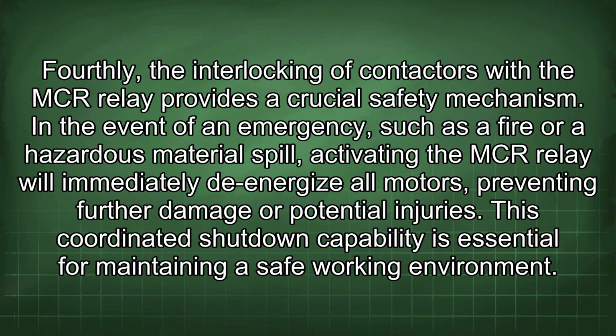Fourthly, the interlocking of contactors with the MCR relay provides a crucial safety mechanism. In the event of an emergency, such as a fire or a hazardous materials spill, activating the MCR relay will immediately de-energize all motors, preventing further damage or potential injuries. This coordinated shutdown capability is essential for maintaining a safe working environment.